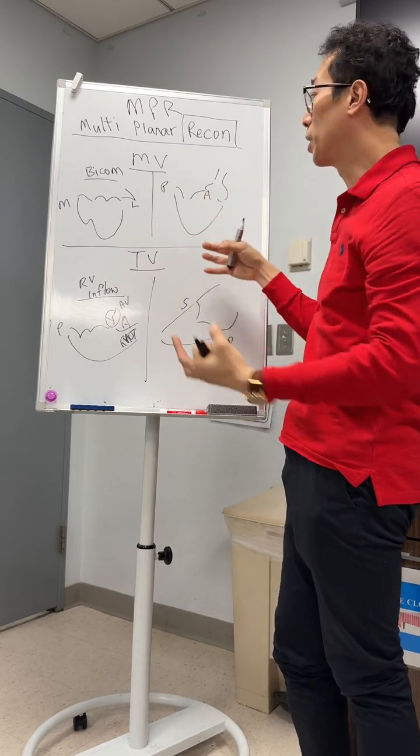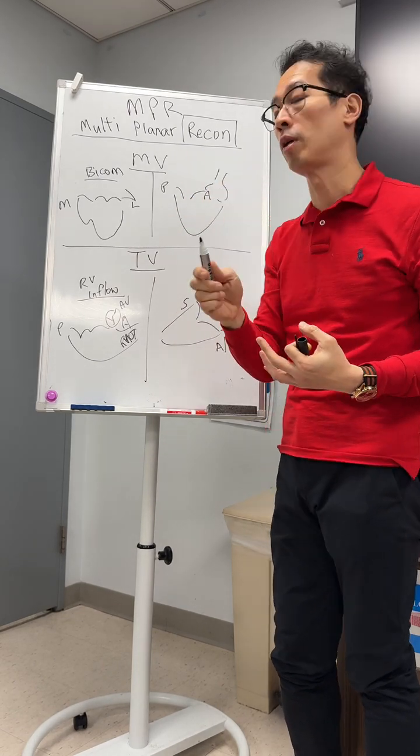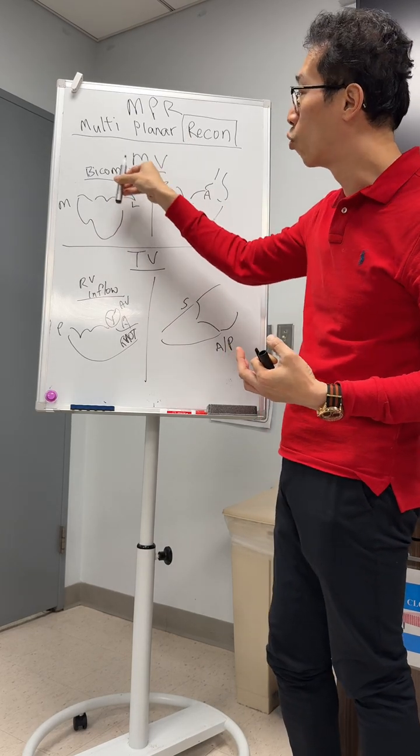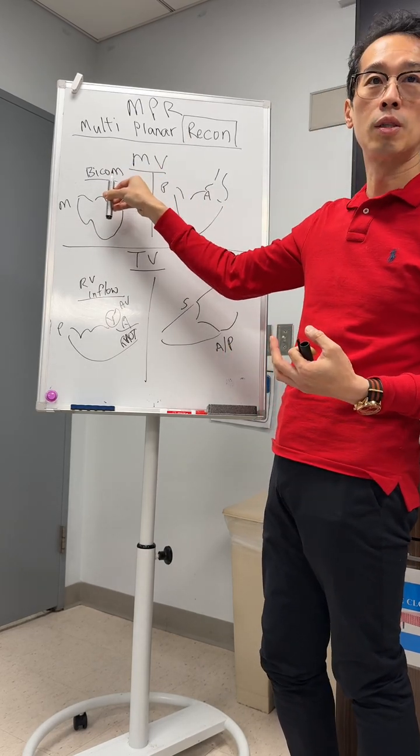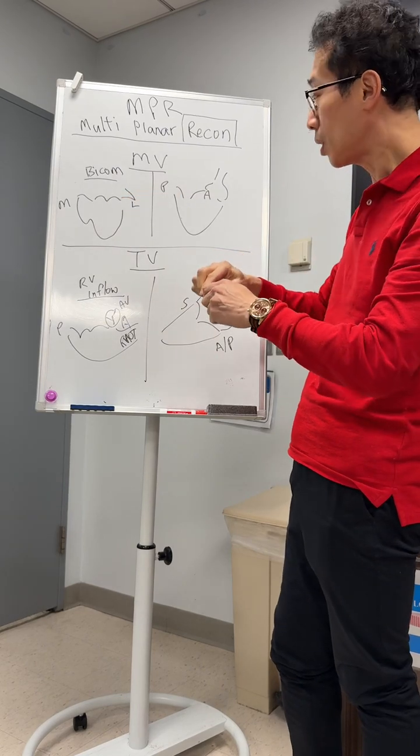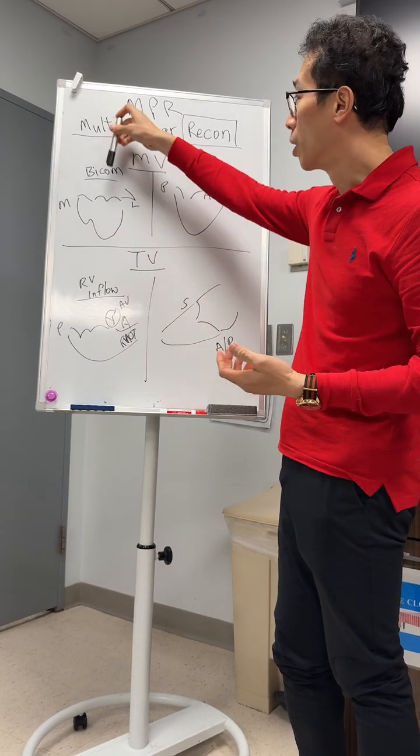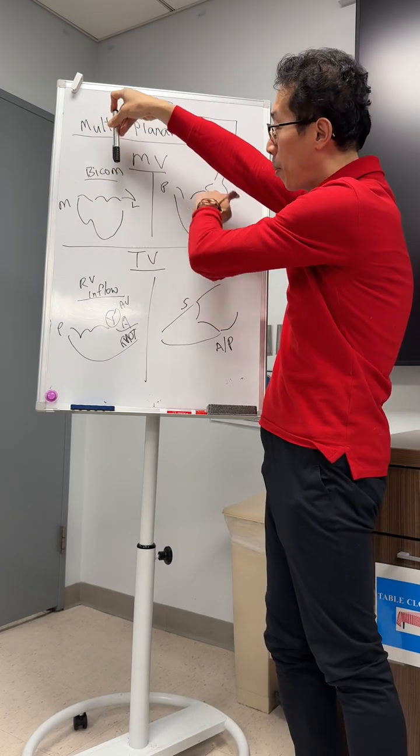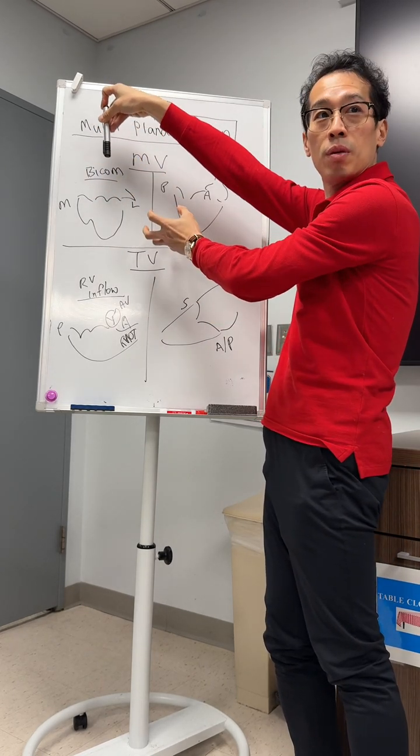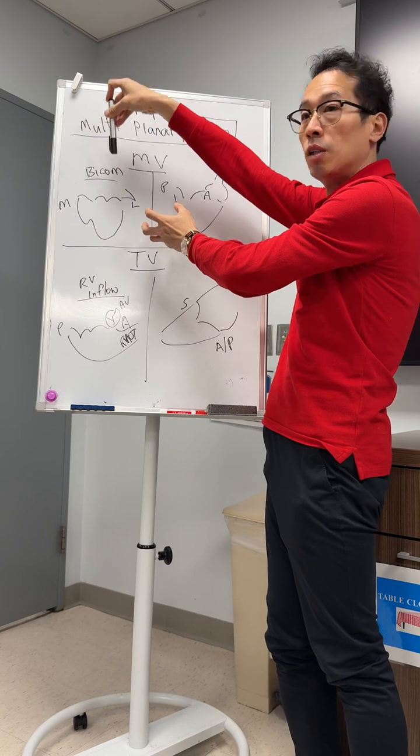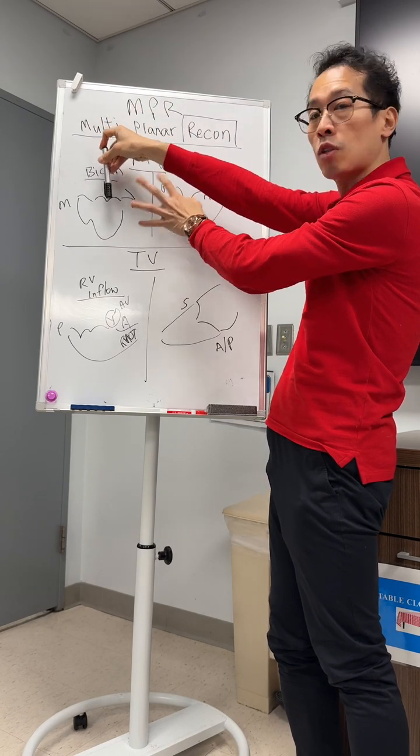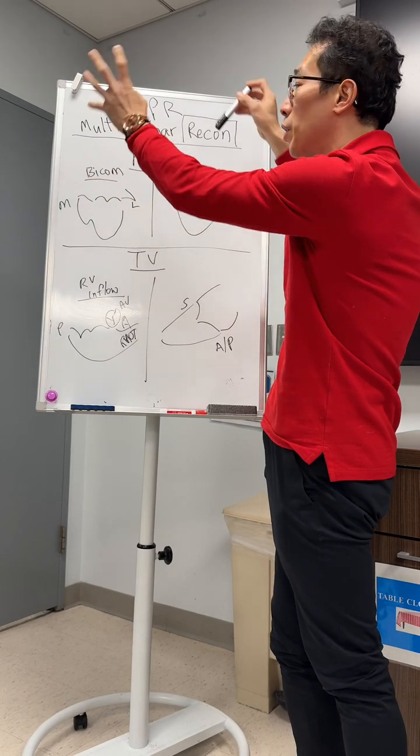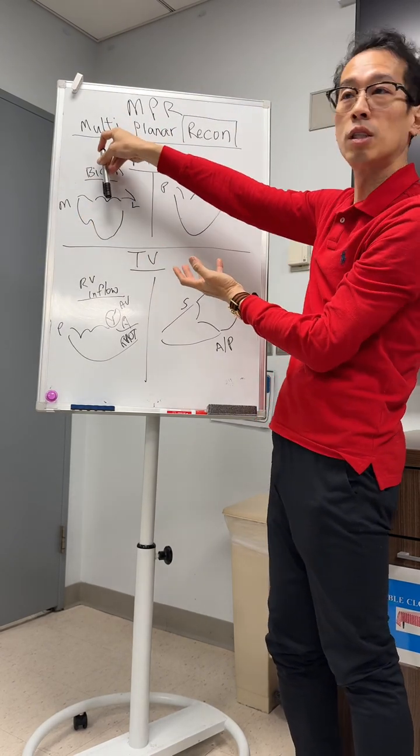The other thing that you want to make sure that it's important to note for MPR is that if you have a device there, the device has to be within your crop box. What do I mean by that? So for example, let's say you're doing it here. If your device is up there, you crop your MPR, you're not going to see this device because it's out of view.